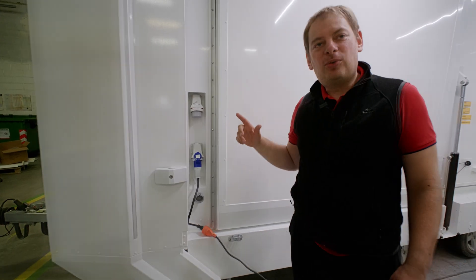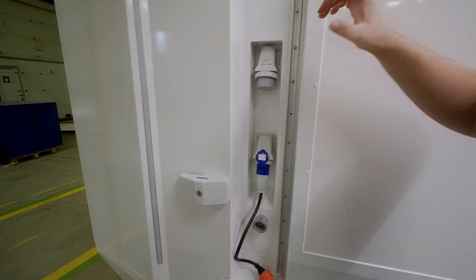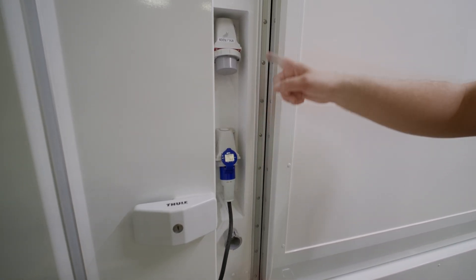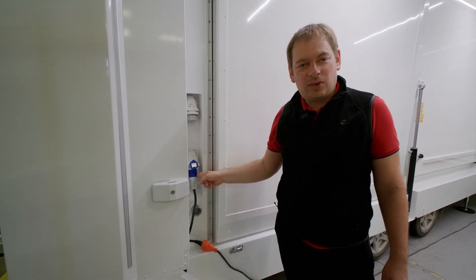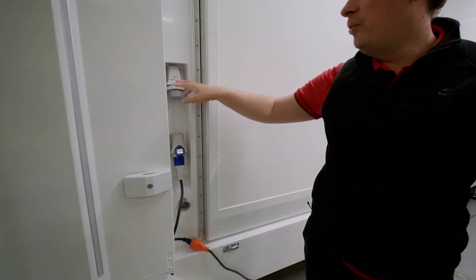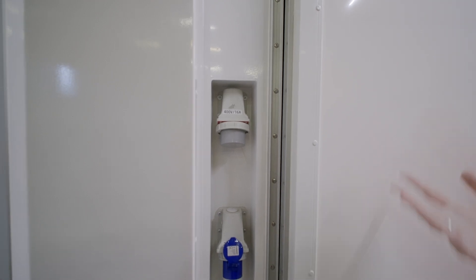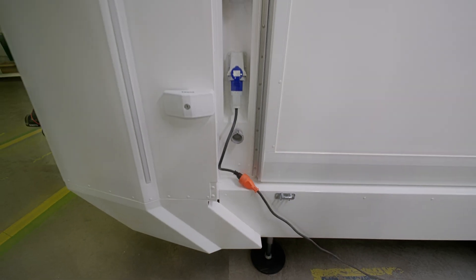That's another small feature — hopefully you'll never need it, but the option is there. The new rolling units come with a new electrical layout for the electrical grid. We now always have two inputs: one three-phase 400 volt, and a simple 230 volt 16 ampere. You can switch between them — so when you only have a single-phase electrical connection available you can still use all the systems, but you need to be careful not to overload the circuit breakers. If you have three-phase power available, you can flip the switch inside the switch box and run the full equipment — two kilowatts per phase or even more — without burning the sockets.